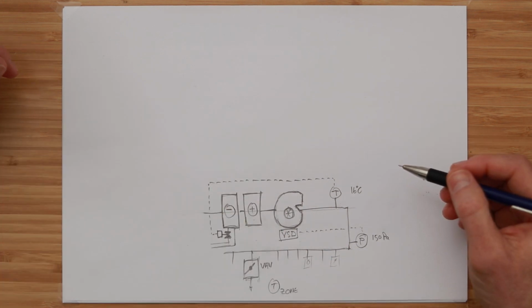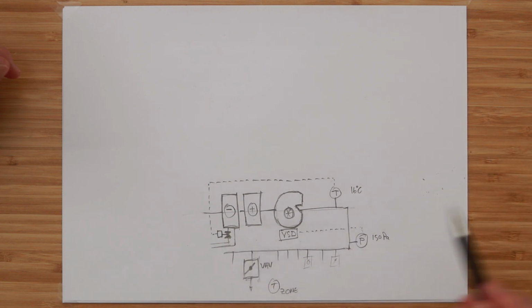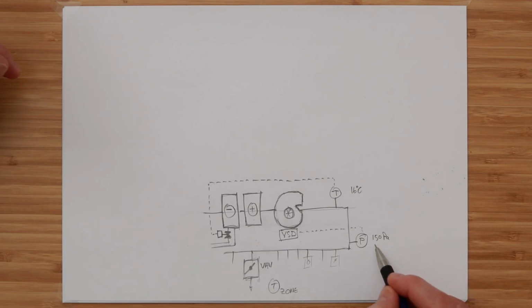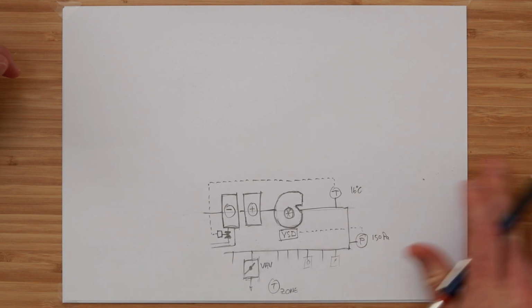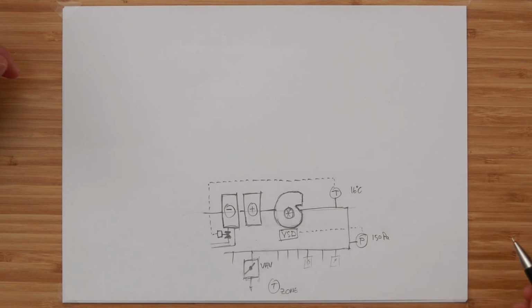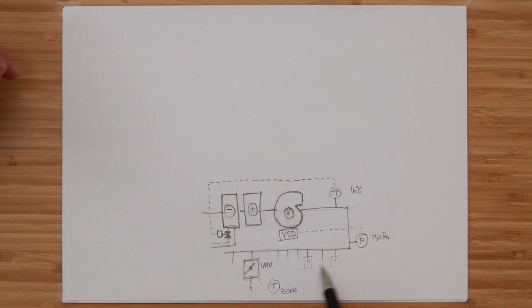So here we have a pretty standard variable volume air handling unit. We have our heating and cooling valves controlling temperature and our fan controlling static pressure. And we have our VAV boxes with our zone temperature sensors. Now in Australia, in every single building, we reset the static pressure set point dependent on the demand from the field. And we reset the air handling unit supply temperature on demand from the field. So we are already optimizing these two control loops as standard practice in building management systems. So the first part of optimization is to get these two set points optimized for the load.